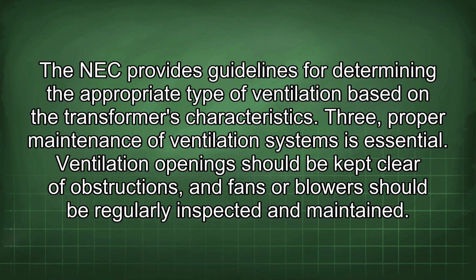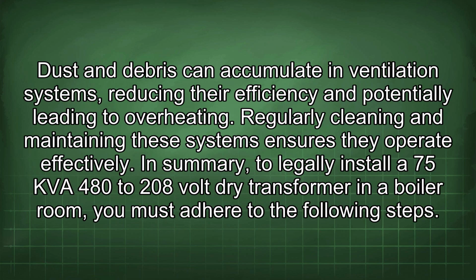3. Proper maintenance of ventilation systems is essential. Ventilation openings should be kept clear of obstructions, and fans or blowers should be regularly inspected and maintained. Dust and debris can accumulate in ventilation systems, reducing their efficiency and potentially leading to overheating. Regularly cleaning and maintaining these systems ensures they operate effectively. In summary, to legally install a 75 kVA 480 to 208 volt dry transformer in a boiler room, you must adhere to the following steps.